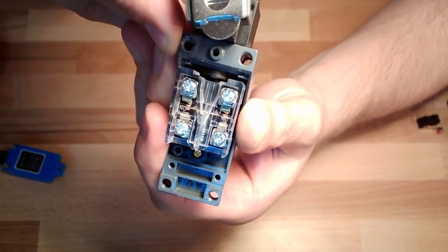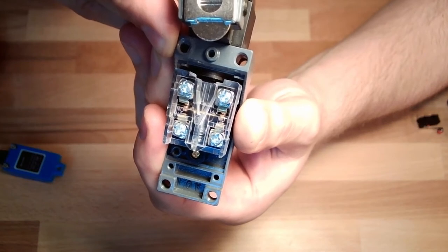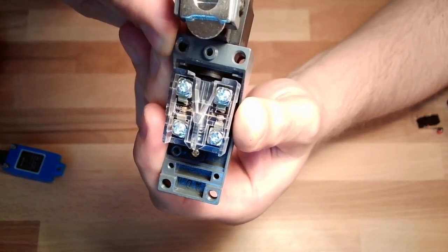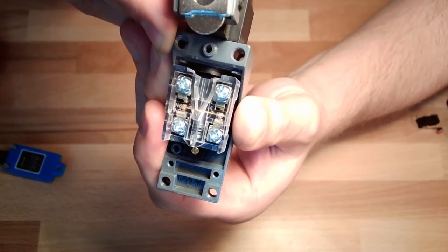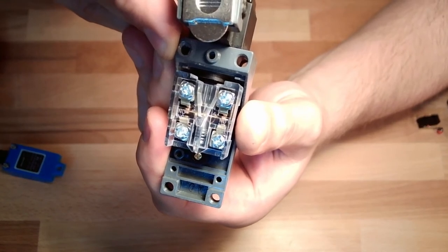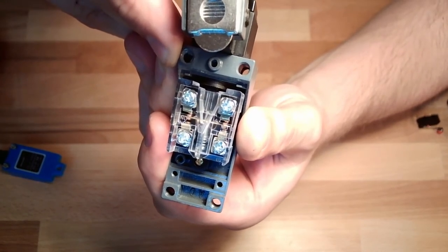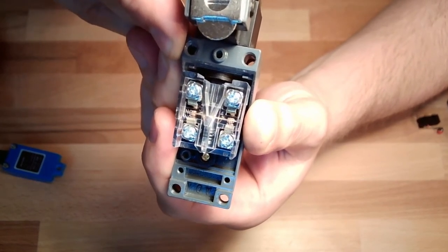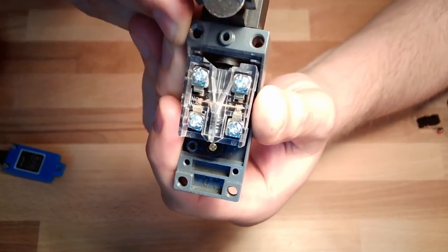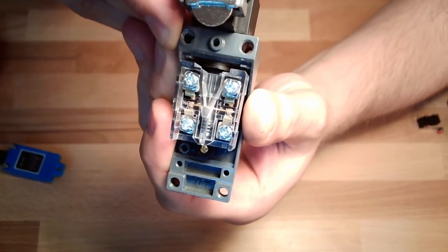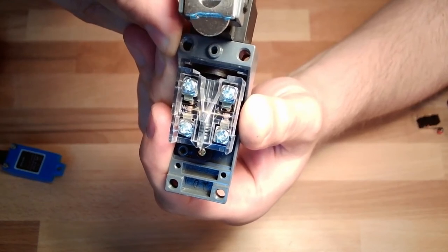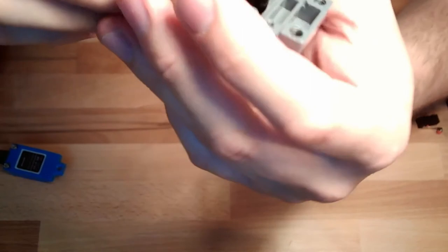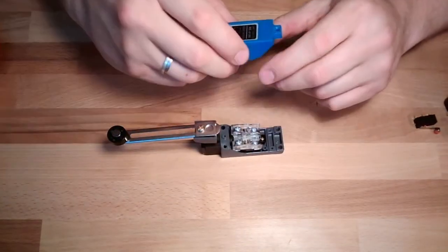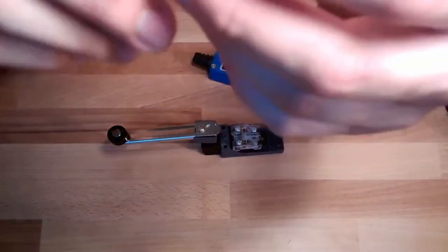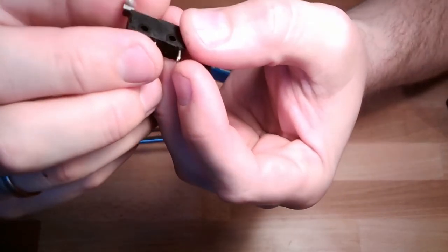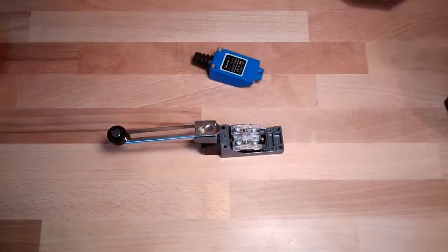And I can move very slowly, only slowly. Let's see. Back. You see? And now I slowly move it in the other direction. Back. Even if I only do gentle changes here, it is just jumping. And this is typical behavior. This is to prevent bouncing or chattering. Schaltprellen, we want to prevent that. Okay? Typical behavior. This is why it always sounds like this.